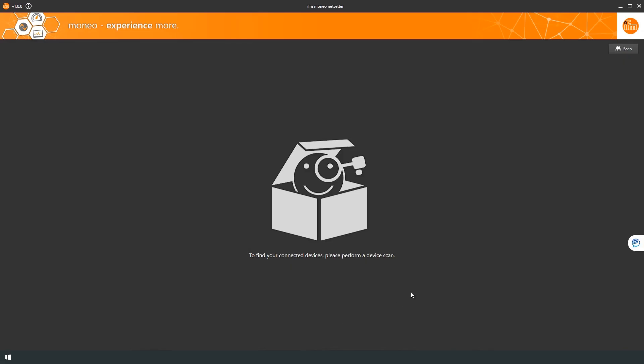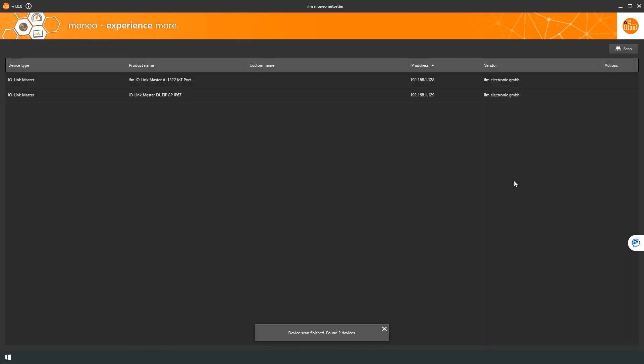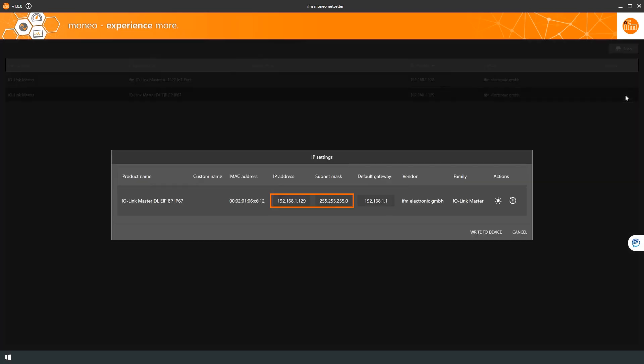After starting the software, the scan button is used to search the entire network. As we have connected the field bus, as well as the IoT port, to the switch in our setup, both are detected by the software. In the following, we will connect the master to the controller via the field bus. This is why we set the field bus address to 192.168.1.130 and thus have brought all components into the same network.